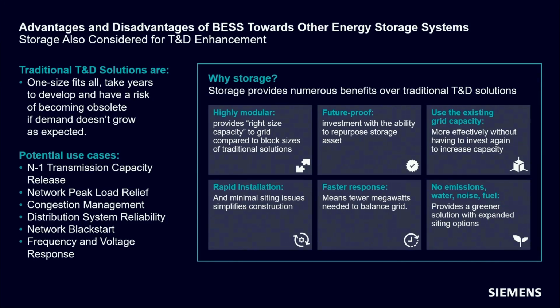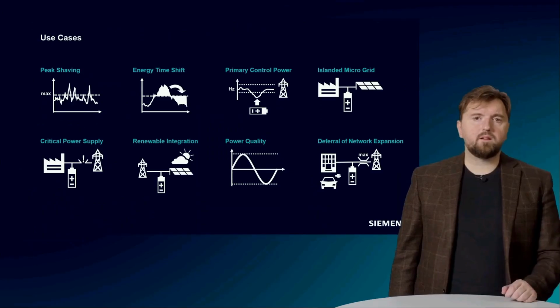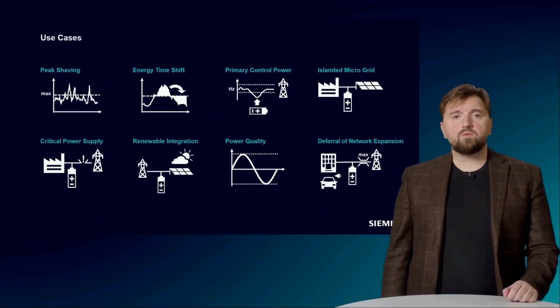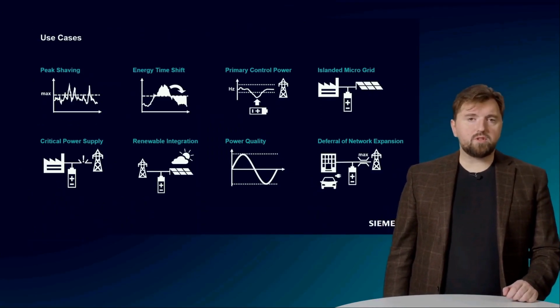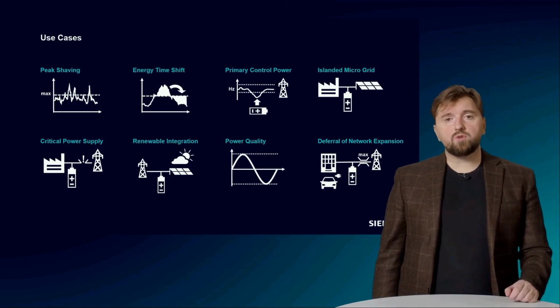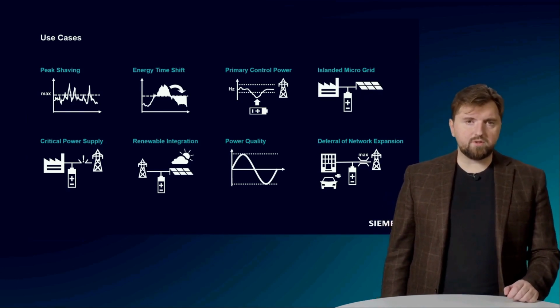BESS projects can be deployed at a fast pace, as we have already seen in the past. When it comes to response rates of BESS, here we can count on a sub-second response time, which makes it a superb choice, especially for frequency regulation. Fast response also means that less megawatts are needed in the system to balance the grid. BESS is also an environmentally friendly choice. BESS systems offer a wide range of functionalities, of which we already mentioned a few. Now let's explore some typical use cases for BESS applications.